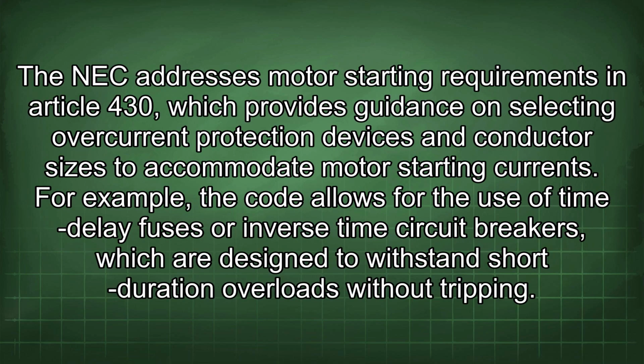The NEC addresses motor starting requirements in Article 430, which provides guidance on selecting overcurrent protection devices and conductor sizes to accommodate motor starting currents. For example, the code allows for the use of time delay fuses or inverse time circuit breakers, which are designed to withstand short duration overloads without tripping.